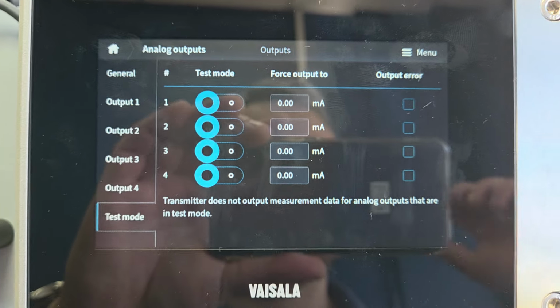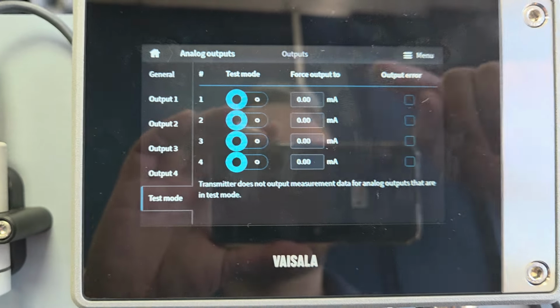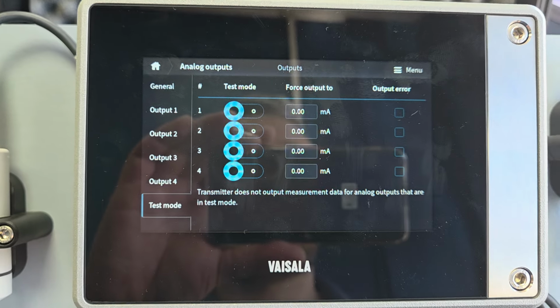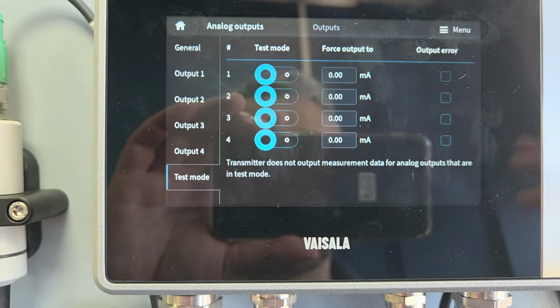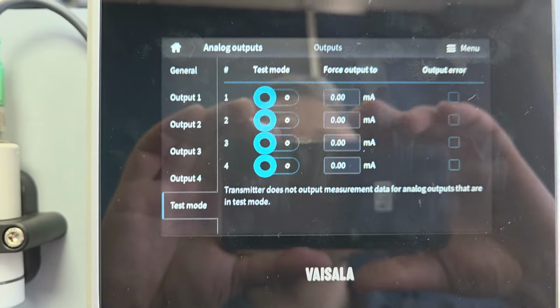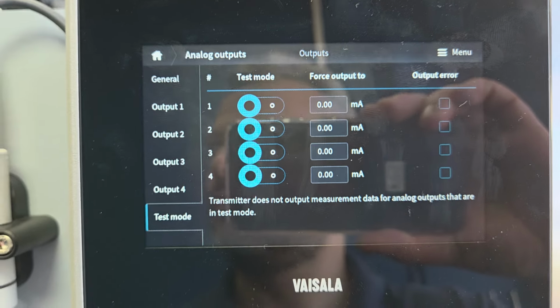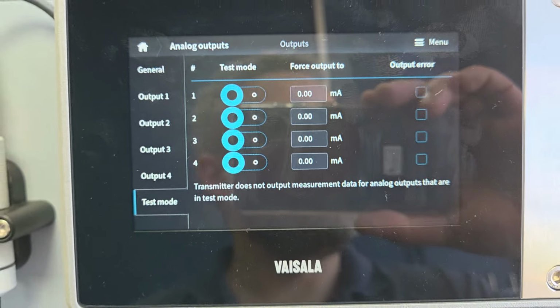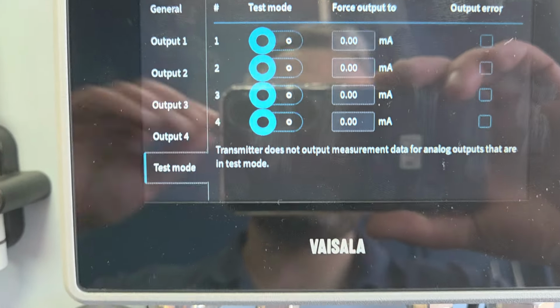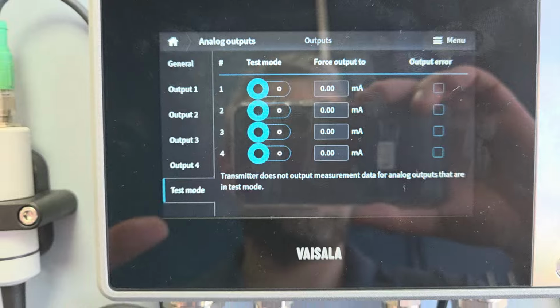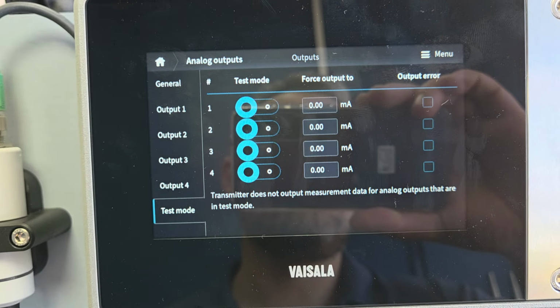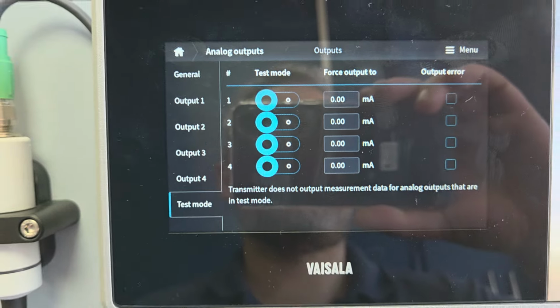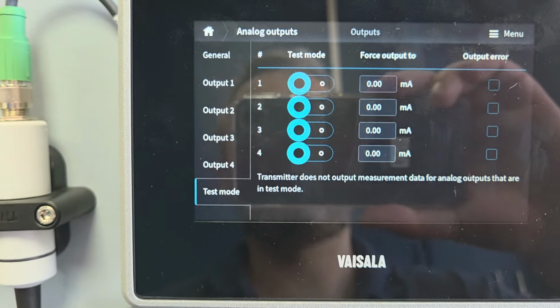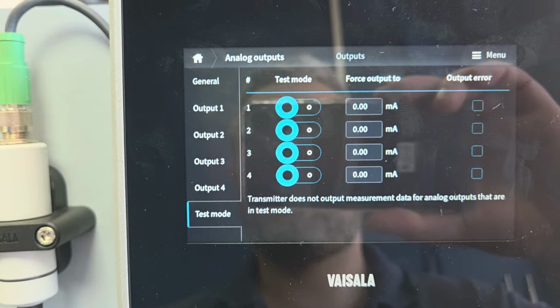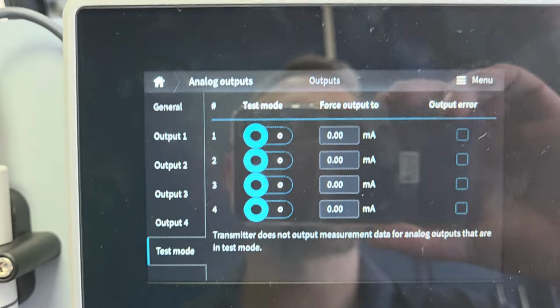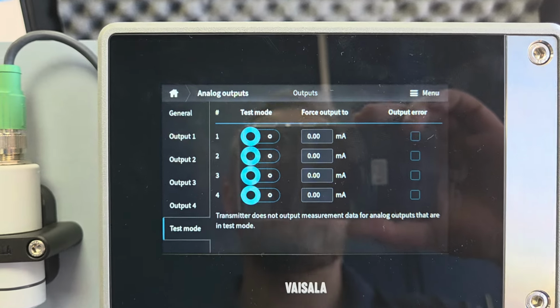So regardless of what your probes are measuring, you could force each of the four 4-20 milliamp outputs to 12 milliamps, 8 milliamps, whatever you want, just to prove that you configured it correctly in your PLC. Quite often we see people saying, the scaling doesn't look right in my PLC, the numbers don't tie up with what's on the display on the transmitter. And you think, well, what's going wrong? So if you set it to 12 milliamps, you can know it's going to be half, and then you can see actually it's because your SCADA system is scaled, instead of being 0 to 100, it's 0 to 150 or something like that. We see that often, so that's a very useful tool.